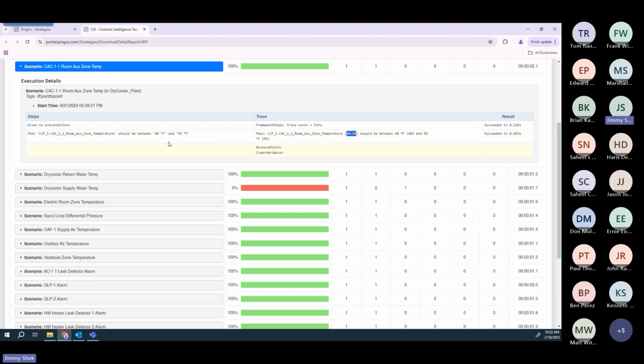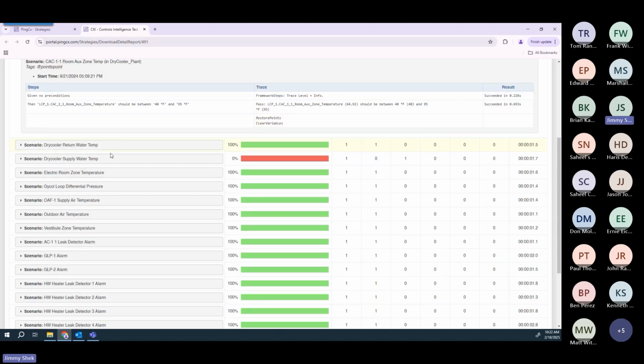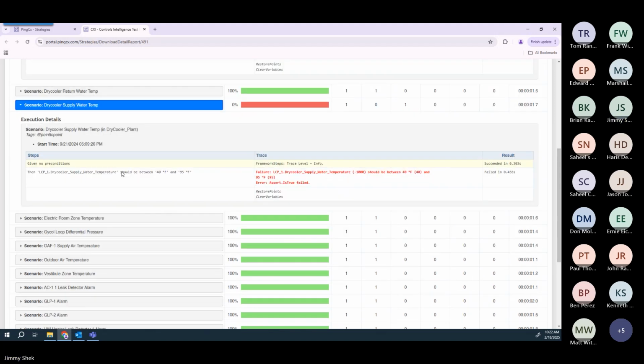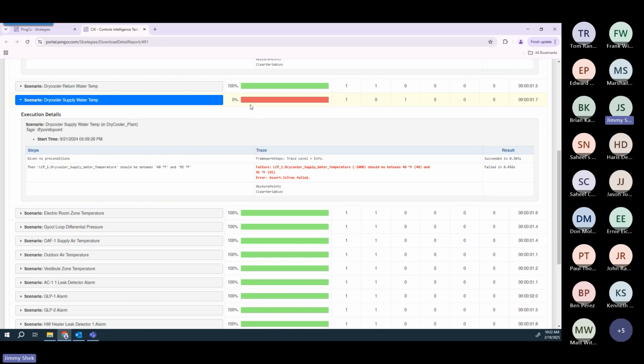In this case, these are just arbitrary values to indicate that we're getting a proper sensor reading for the zone temperature. In comparison, if we take a look at one of these test cases that failed, you'll see a similar test scenario, a point-to-point check, but in this case it's looking at the supply water temperature, checking that it's between 40 degrees and 95 degrees. And in the trace, when it goes out and tries to read that temperature, it's getting a value of -1,000. Obviously, that's not within the range of 40 and 95, and thus that test case fails.